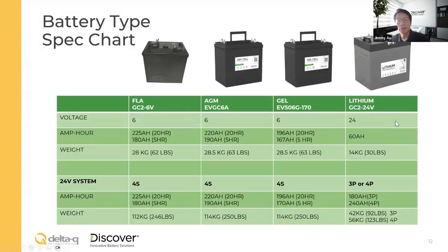This one here gives you a better picture of, again, a comparison of the different technologies, but in the same form factor. So the group size you see here is what we call a GC2 size. You will recognize this and find it common in places like golf carts, electric scissor lifts, pallet walkies, floor scrubbers. So generally it's a 24-volt system and you might see 4 of them. If you look at the lead acid family, which is the flooded, AGM, and gel, they're all 6 volts in this case. Amp hour wise, they're all more or less the same as well. They range from 200 amp hours up to 225 amp hours. That's how much capacity you can pack in this form factor.